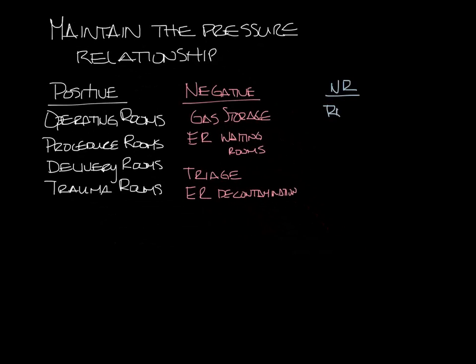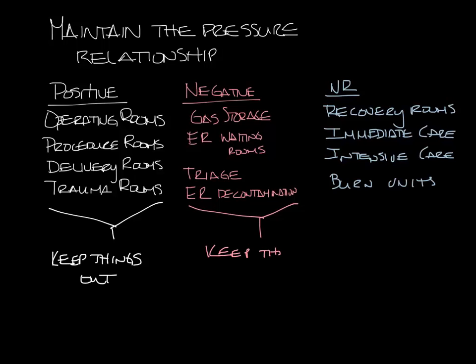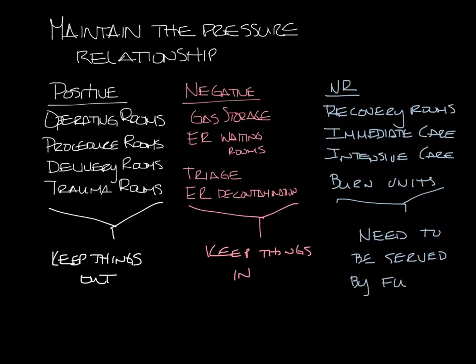There are also some areas that have no pressurization requirement, such as recovery rooms, immediate care areas, intensive care areas, and burn units. Table 7.1 is three pages long so there are a lot of other areas not on this list, but you get the idea of what types of spaces are kept positive or negatively pressurized. You can see that operating rooms are positively pressurized to keep things out of the space, and gas storage is negatively pressurized so that if something happens in the space the gas doesn't get out. There's also a statement in ASHRAE 170 that says recovery rooms, intensive care areas, immediate care areas, and burn units do not require pressurization relationships to adjacent areas, but they do need to be served by a fully ducted return or exhaust system.